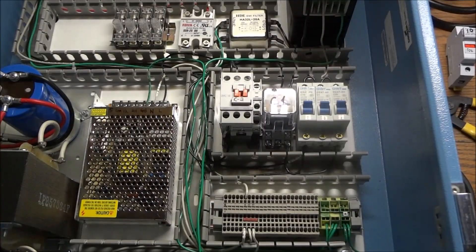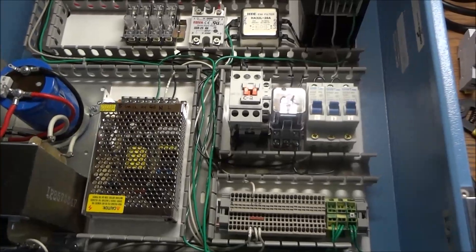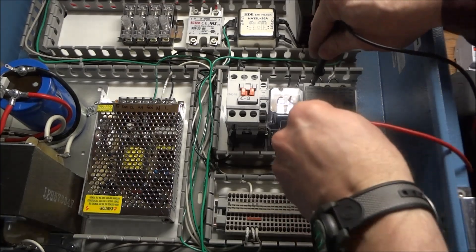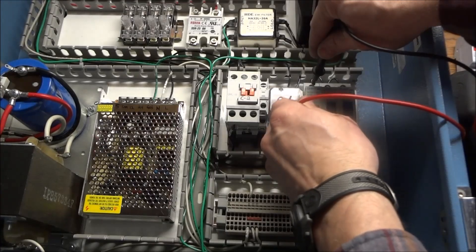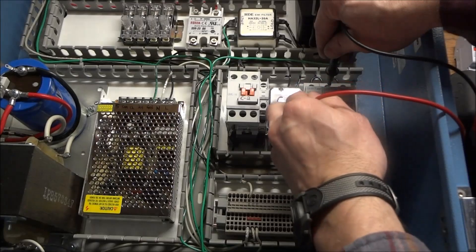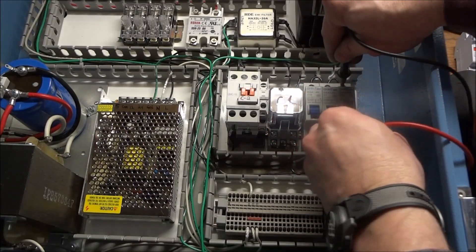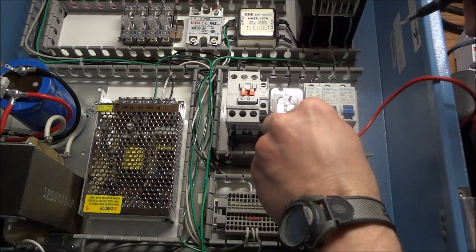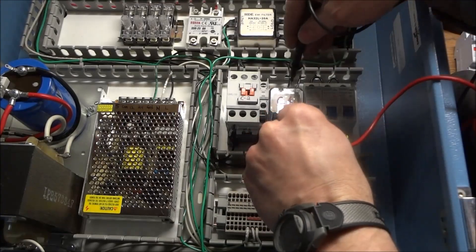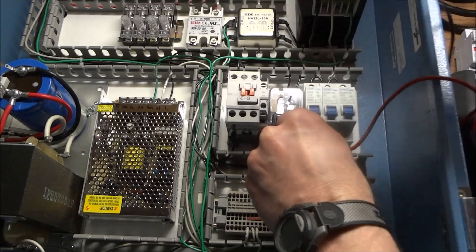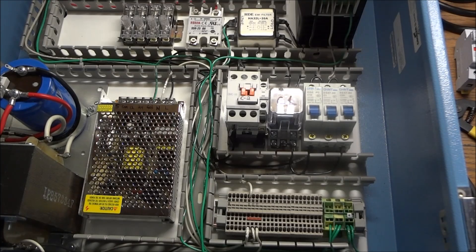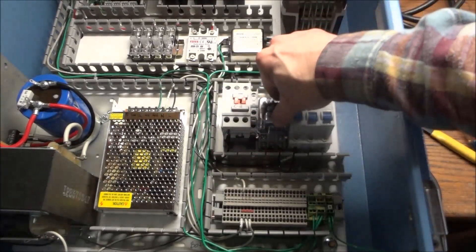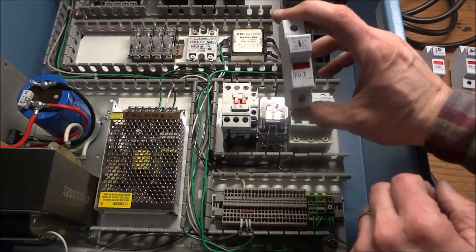Okay, now that we've had that retrofitted we can move on with the wiring. Check this with a meter just to make sure. All right. All right. All right, the breakers are working and we've got power over here. And do we have power through? Nope, that's our normally closed contacts. Okay, so now we've got our panel retrofitted with our new C1 contactor and circuit breakers instead of our fuses.